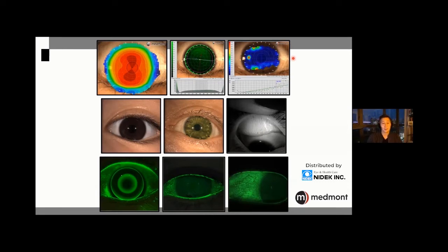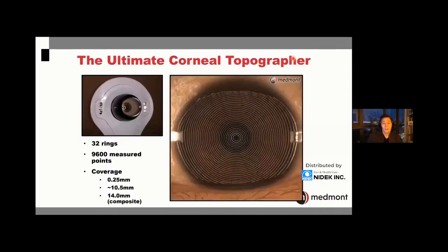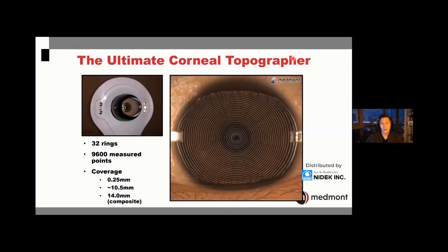You're probably familiar with the Medmont Topographer being accurate, but now with the Medmont Meridia, you have a device that takes very high resolution images of the entire anterior segment. It's a 32-ring Placido Topographer that stretches rings to the far periphery of the cornea — one of the advantages of a small cone instrument. You're able to shorten the focal distance and push that ring reflection to the far periphery, giving a large surface area of capture. If those data points are accurately interpreted, we get very accurate topography, which the Medmont is well known for in many studies.